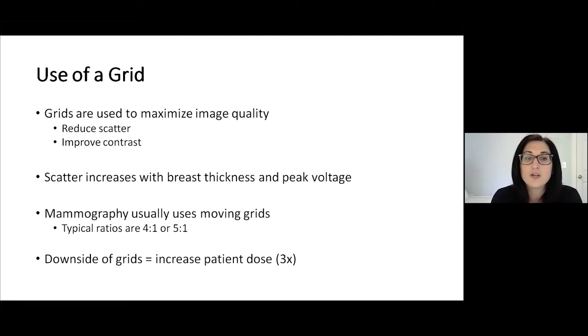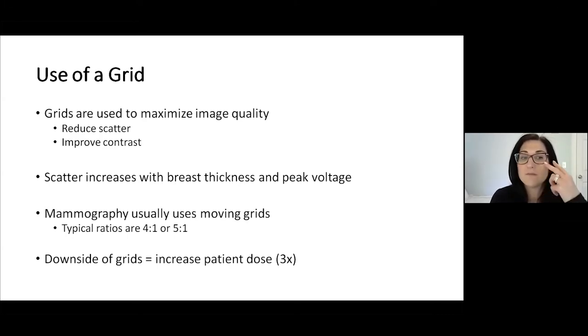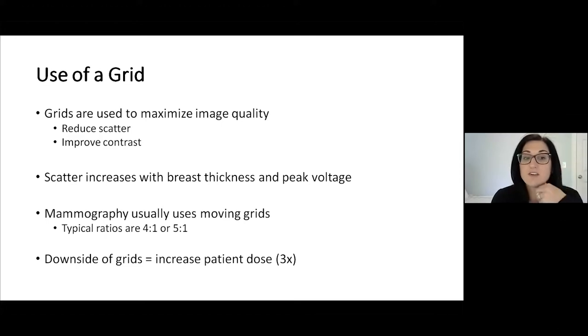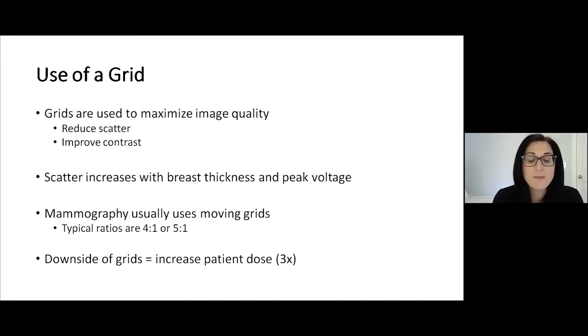Grids are used for two purposes. Their main purpose is to maximize image quality, and they do this by reducing scatter, thus improving contrast. Scatter increases with breast thickness and increased peak voltage, so the thicker the breast, the more necessary it is to use a grid to decrease scatter. Mammography usually uses moving grids, and the typical grid ratio is 4 to 1 or 5 to 1.